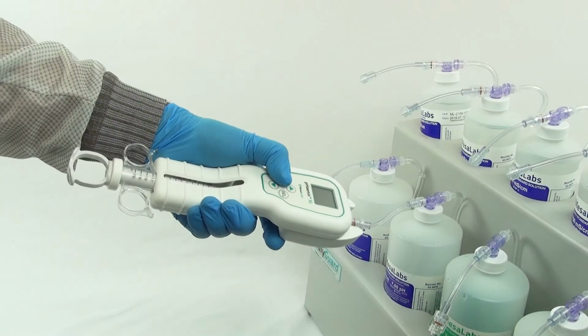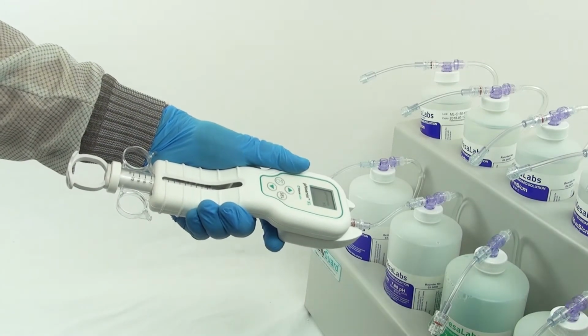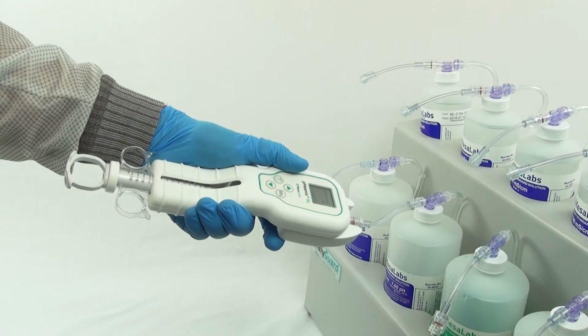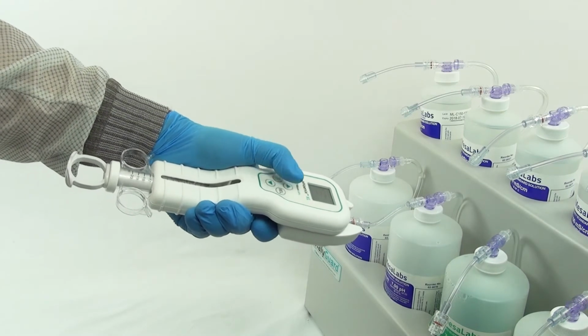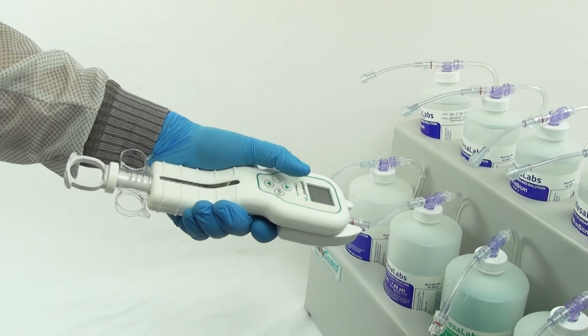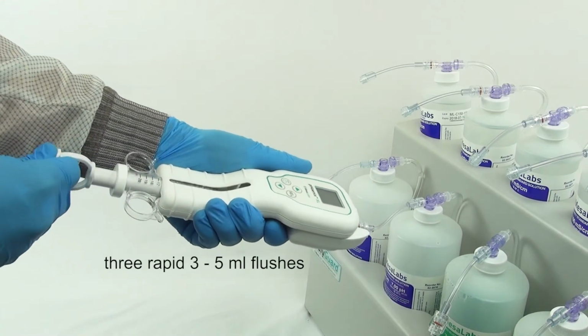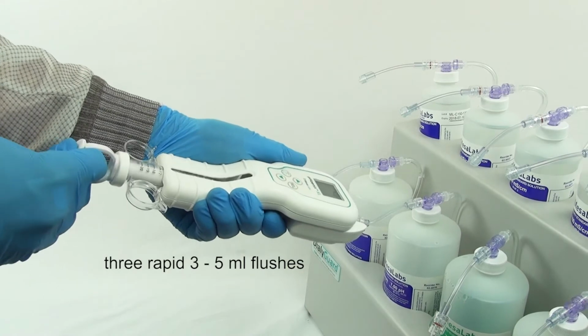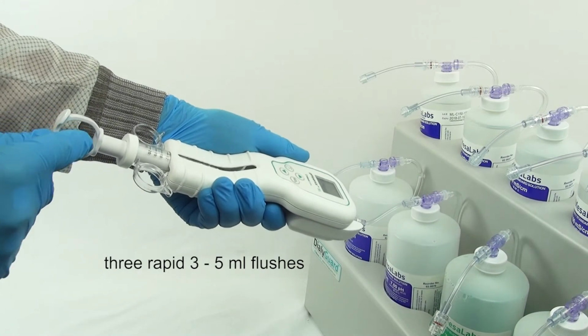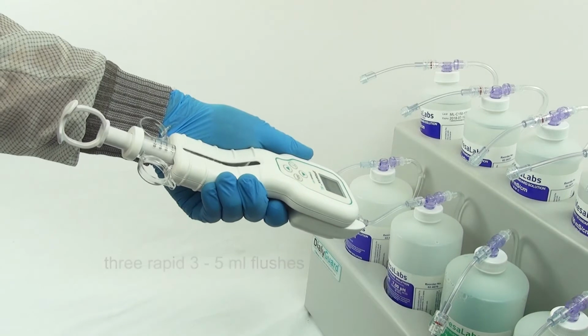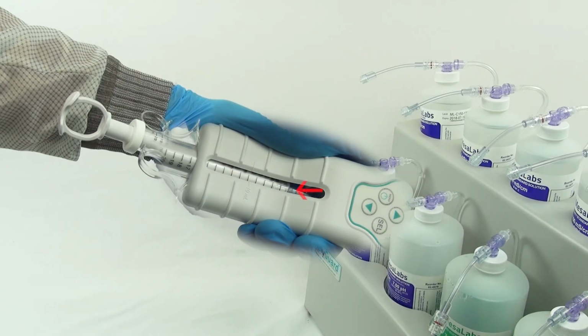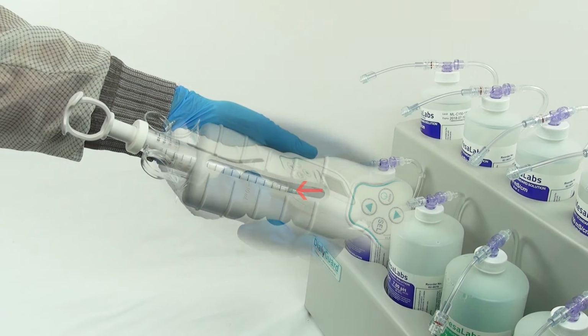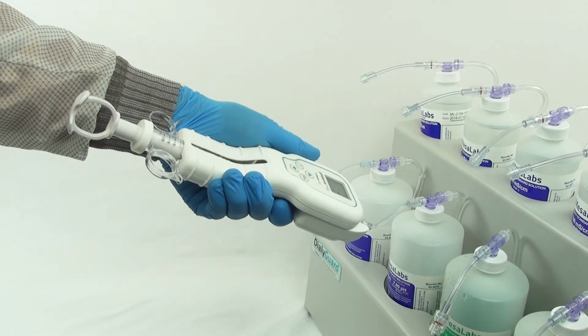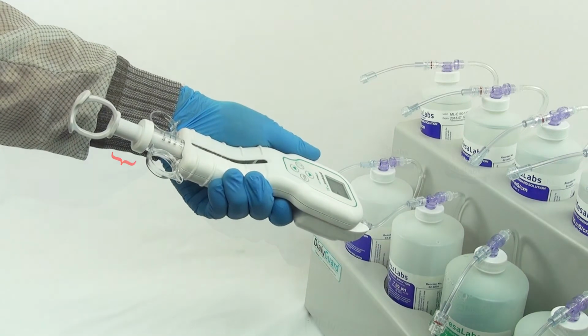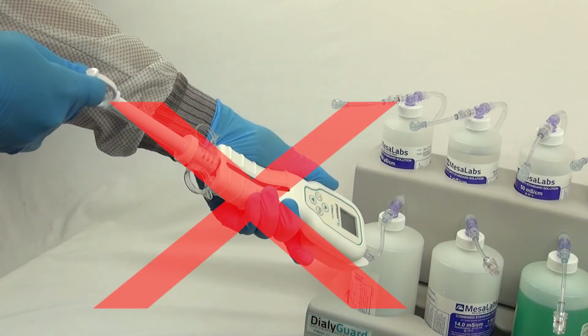Before each calibration, we recommend flushing or rinsing the meter to get rid of any remaining fluid or air bubbles from previous solutions. When introducing a different solution to the meter, be sure to use 3 rapid 3 to 5 milliliter flushes for optimal results. Remember that drawing 3 to 5 milliliters of solution means the blue part of the syringe goes to the first line on the handle of your meter, or when the end of the syringe has been pulled out roughly half an inch. When flushing, make sure that your draws are not too slow or too long.